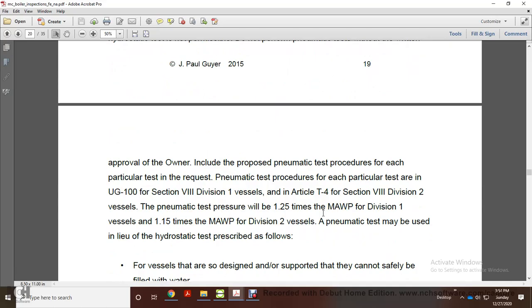Pneumatic test procedure: each of the particular tests is covered in UG-100, Section 8, Division 1 vessels, and Article T-4, Section 8, Division 2 vessels. Pneumatic test pressure is 1.25 times the maximum allowable working pressure for Division 1 vessels and 1.15 times the maximum allowable working pressure for Division 2 vessels.